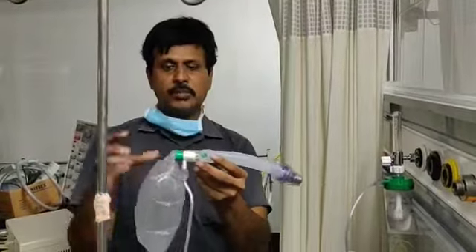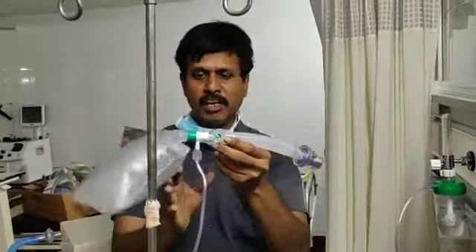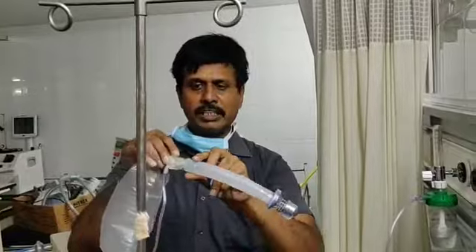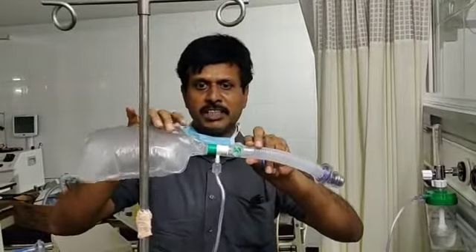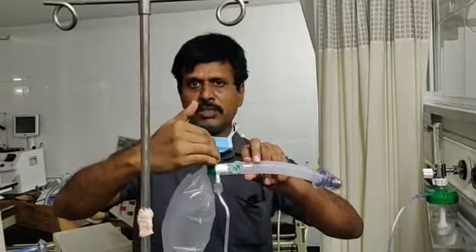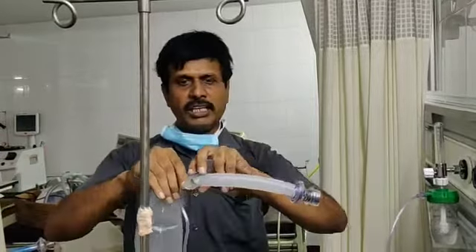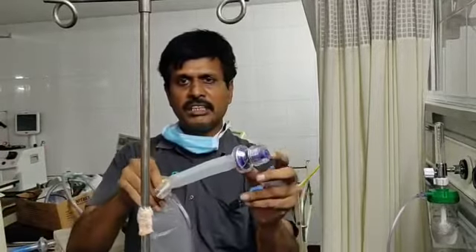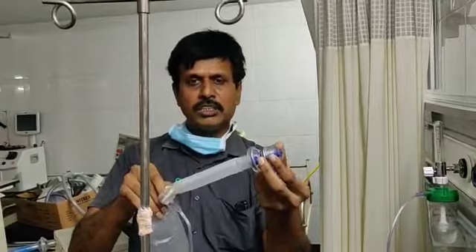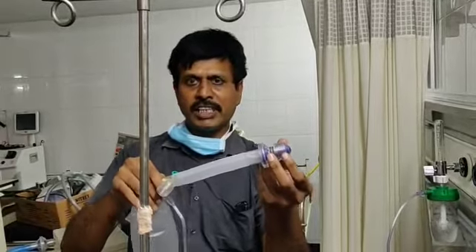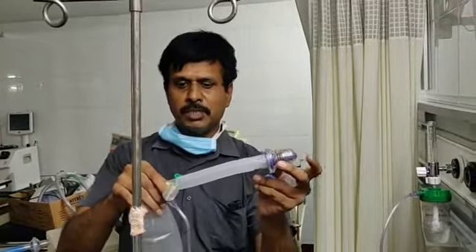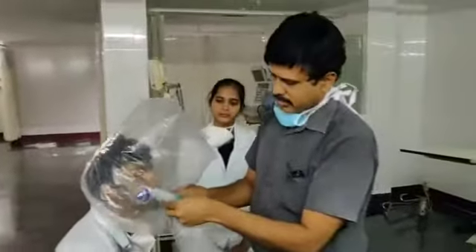And to the T-piece, I connected the reservoir bag. Oxygen is coming from here. This will be only for inhalation. The valve inside will not allow the gas to come out of this, and the exhaled air will come out of this. At this end, I put the PEEP valve. So if I set 5 or 10 or 15, I can keep that, and that will be the CPAP. Now I have connected this to the patient.